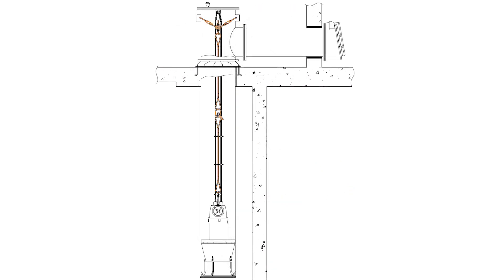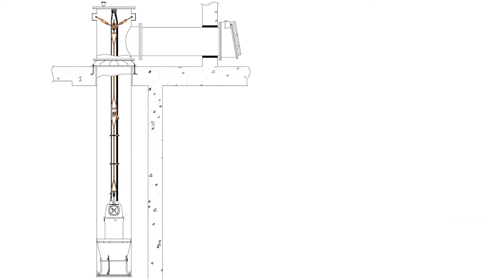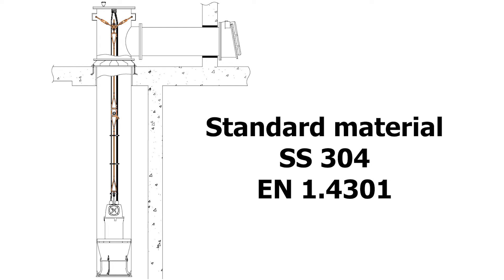The cable suspension system is application-specific, as it depends on the diameter of the column tube, the height from the top of the column tube down to the lifting bracket on the pump, and the number and diameter of the power cables. Therefore, the cable suspension system is made to order and cannot be put on stock. The standard system is made in stainless steel 304 EN 1.4301.